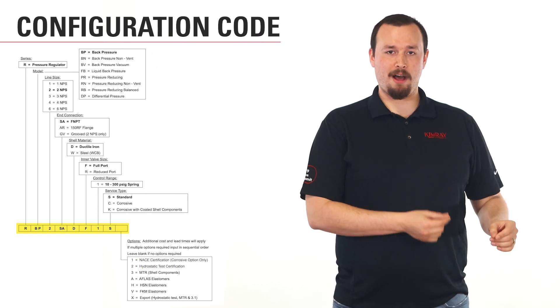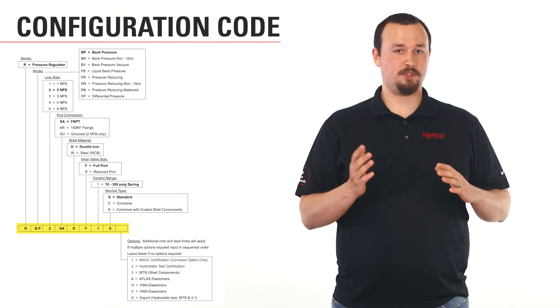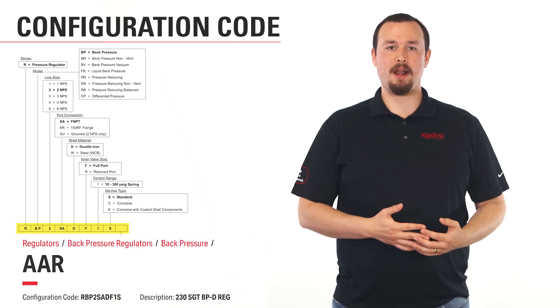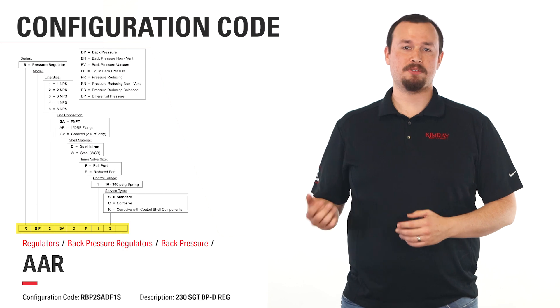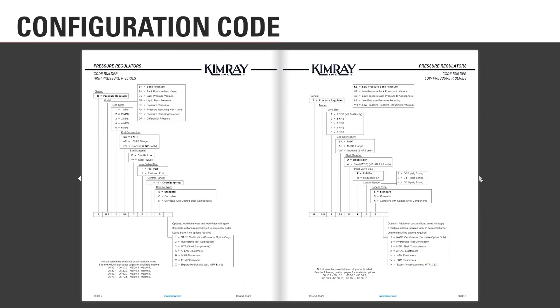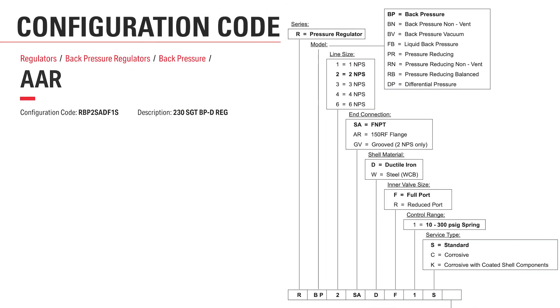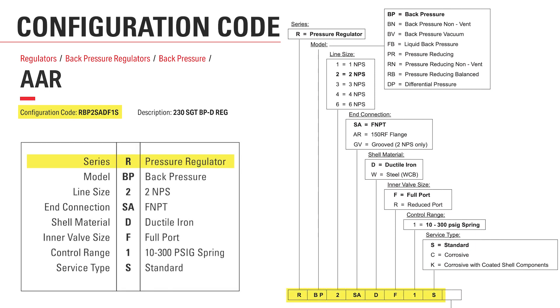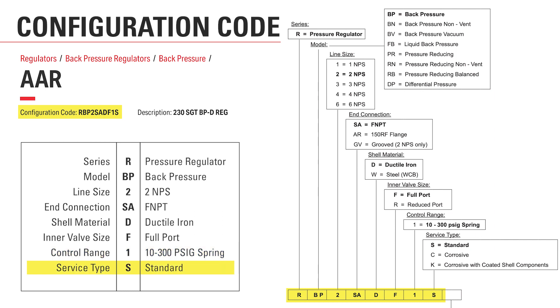The configuration code is not on the valve — it's simply how you build a valve to order. This is the newest naming convention for Kimray and began in 2020 to better align with industry standards and improve customer experience. The code builder charts are included in the front pages of each catalog section and allow for the most precise naming of a product, including all the needed information in one strand of letters and numbers. In our AAR example, the standard configuration would generate a code meaning: a pressure regulator series, back pressure model, with two-inch line size female NPT connections, ductile iron shell material, full port inner valve size, with 10 to 300 pounds per square inch control range, operating for standard service type.